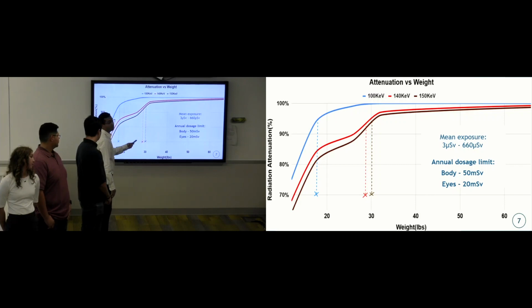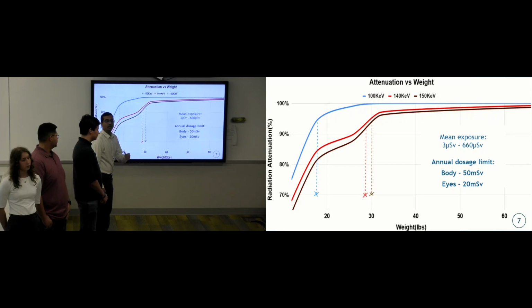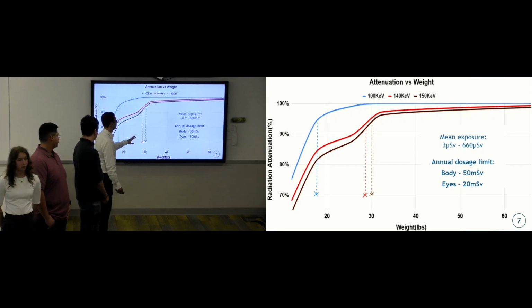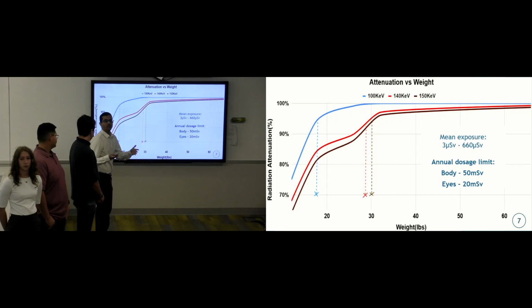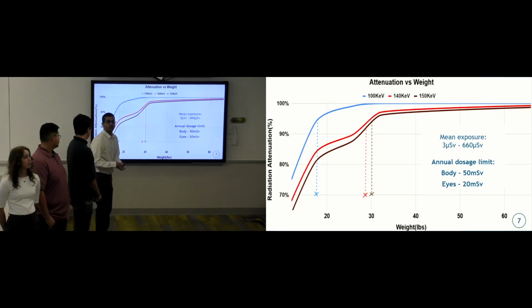To account for these things, we have a radiation sensor built into our shield, which works on scintillation detectors. It converts the radiation to visible light, and then through an electric signal to a photodiode, that measurement gives us an estimate of how much radiation the doctor is being exposed to, and we can warn the doctor if the radiation exposure exceeds the threshold.